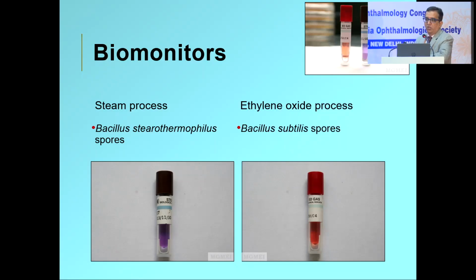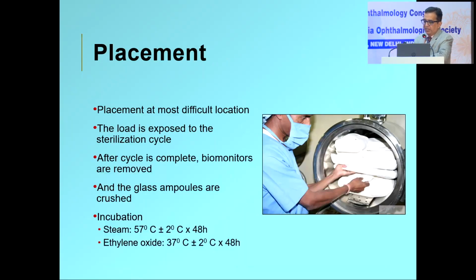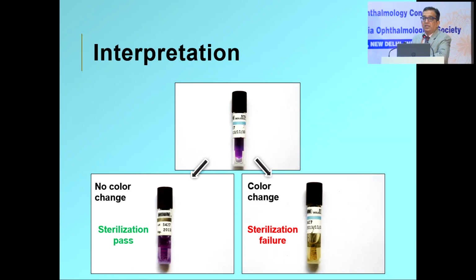So if you have an EO gas also, the EO gas and the steam autoclaves, they have different biomonitors. And both these biomonitors are placed where? They are placed at the most central part of the load, where the steam would have the most difficulty in penetration. And once you put this vial inside the load, get the sterilization completed, and you take it out, then there is a small ampule out there. So you see this blue media, so that is the media, and inside the media there is a glass ampule. So you squeeze on the glass ampule, and the spores that are present within the glass ampule will come into the media.